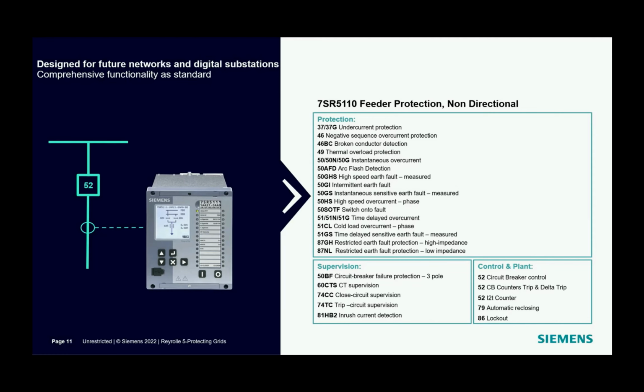Measured earth fault protection, which is slightly different from calculated earth fault protection, is directly measured from a neutral CT or residual connection to three line CTs, and it uses the suffix g after the function number. So calculated earth fault protection is 50n, and measured earth fault protection is 50g. And high-speed intermittent and sensitive earth fault protections are 50GHS, 50GI, and 50GS. It has also a user configurable automatically closing function, 79, or shortly, auto reclose.